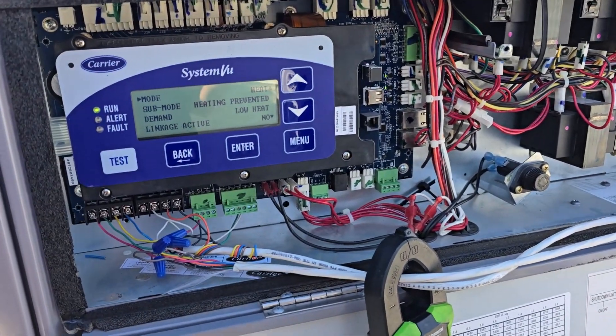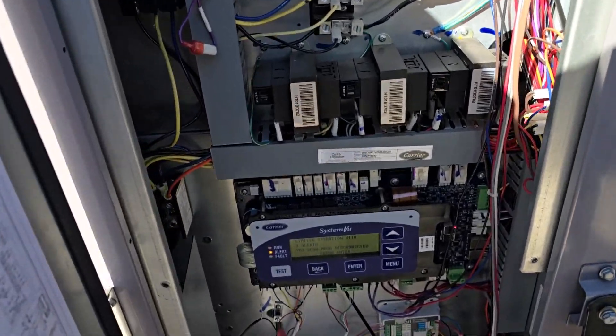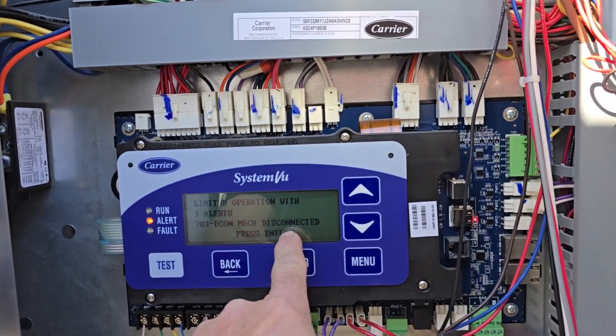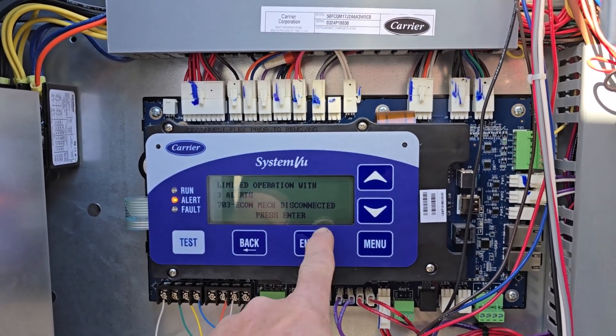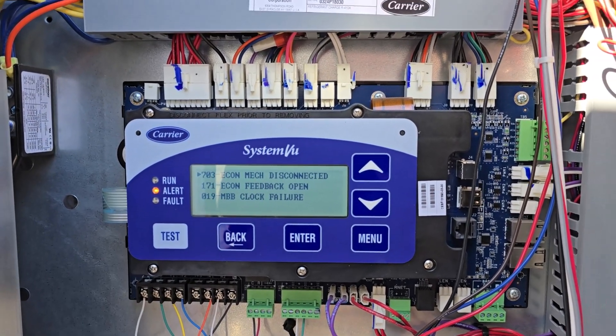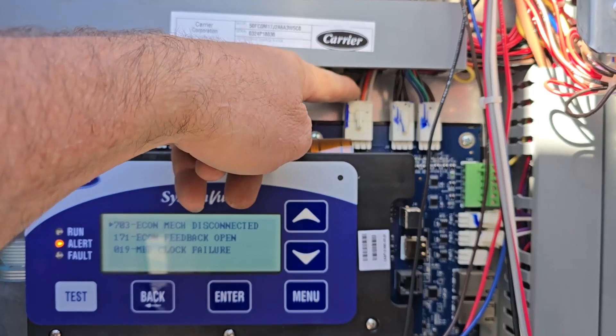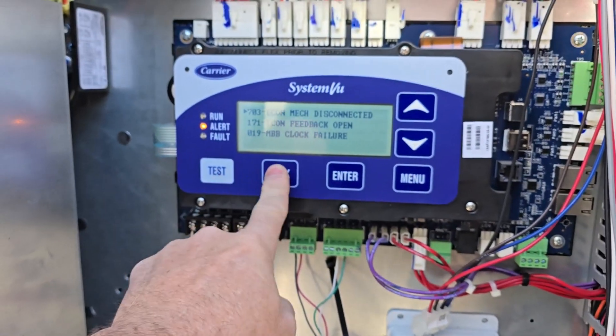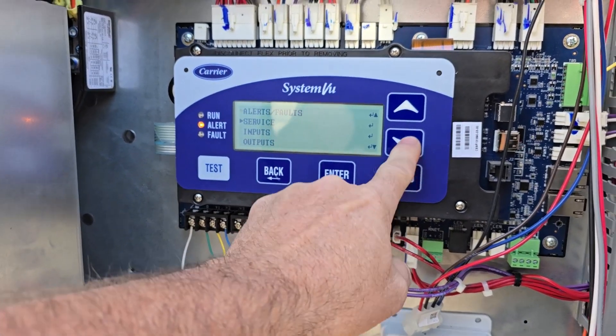Another unit next to that one also has SystemVu, so of course it has alerts — mechanical disconnect, econ mechanical disconnected. Here are the faults, and again here are the input/outputs for that stuff. These people took over the economizer too, so we'll do the same fix on this one.